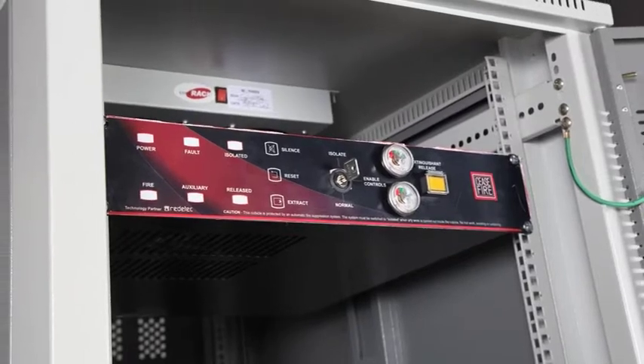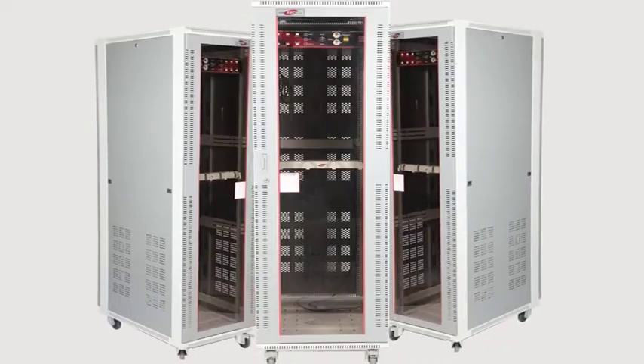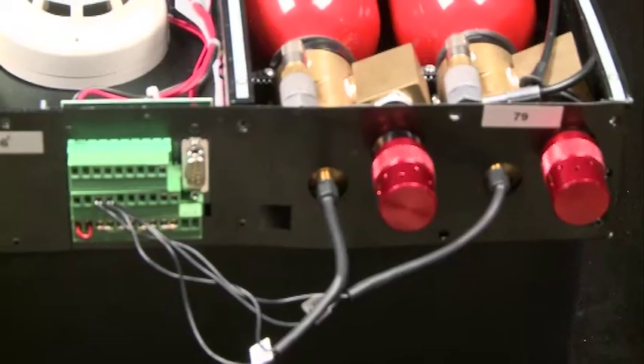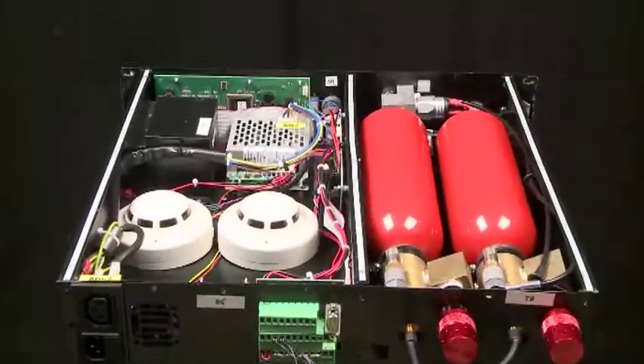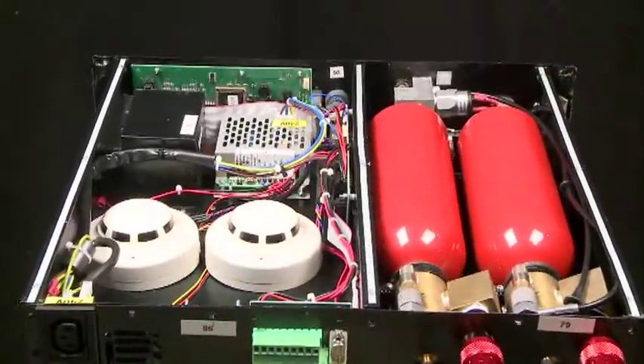Here's how it works: The Ceasefire SQRS is installed within the micro environment of a server rack. When the detector senses a rise in temperature above normal levels, or particles of smoke, or a change in the quality of air in the contained service space, the detectors activate the system.